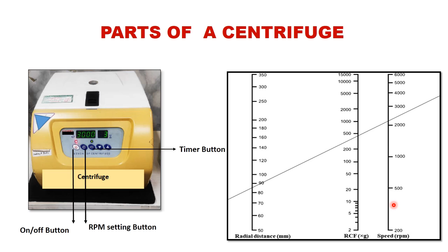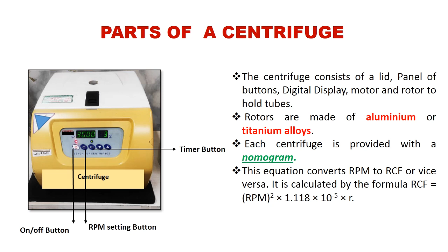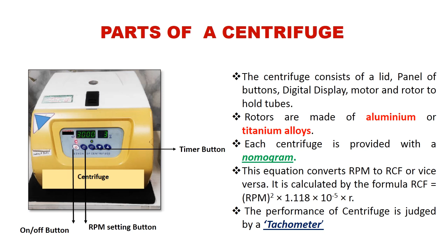In some SOPs, the speed is given as RCF expressed as small g. In some SOPs, it is given as RPM. This equation converts the RPM to RCF or vice versa. It is calculated by the formula RCF equals RPM squared into 1.118 into 10 to the power minus 5 into R, where R is the radius at which the rotor is located away from the motor. The performance of a centrifuge is judged by a tachometer.